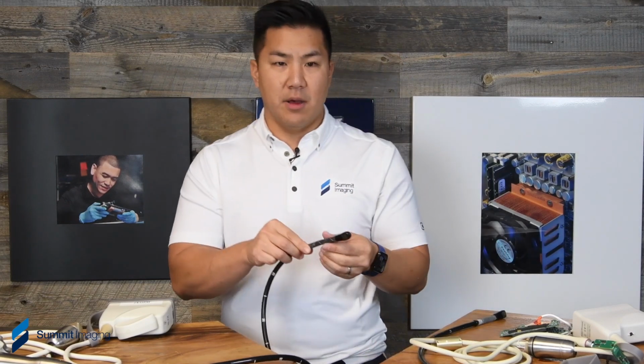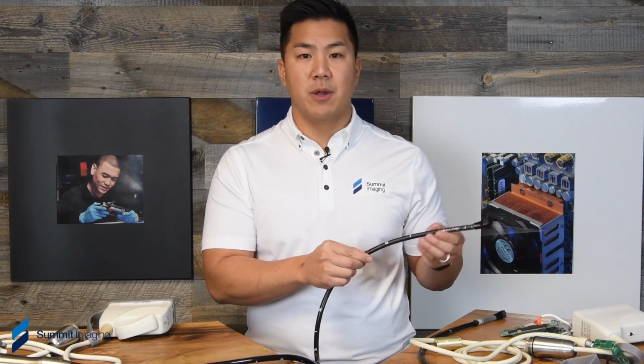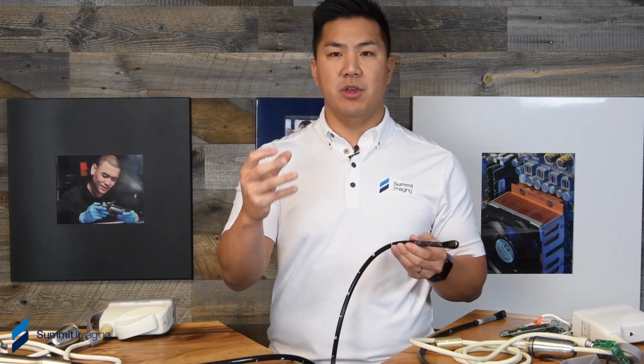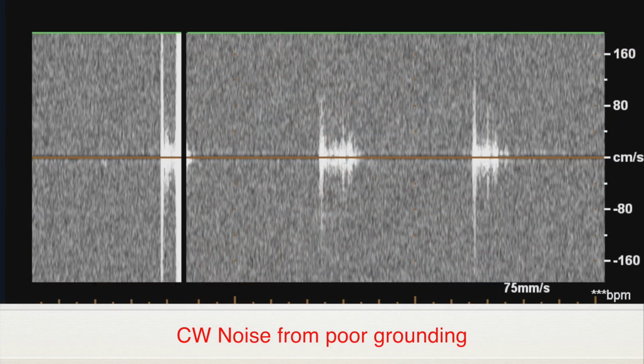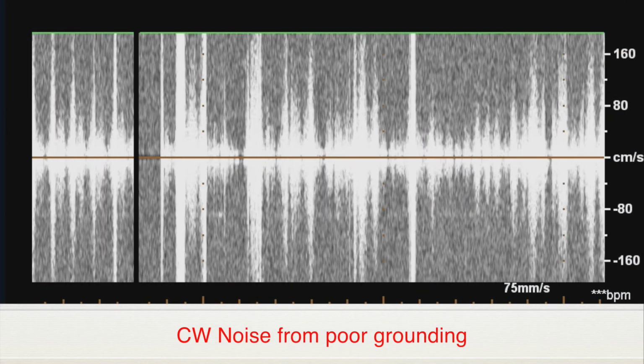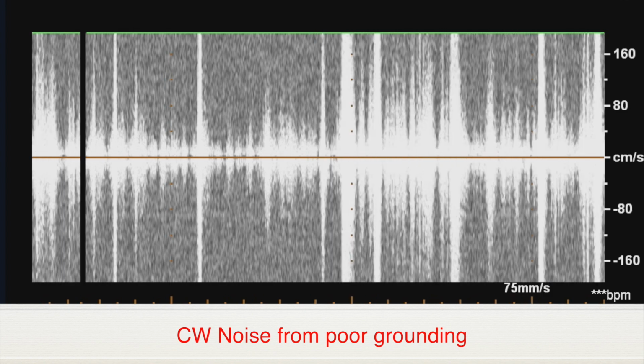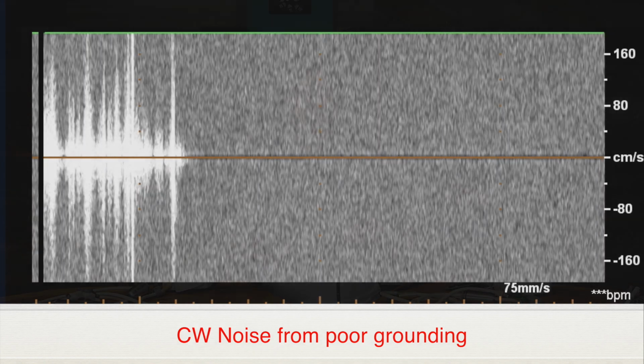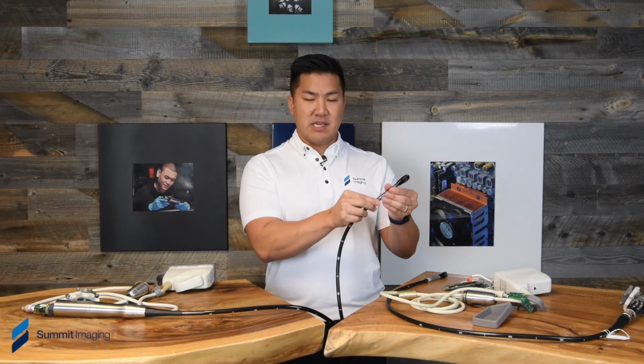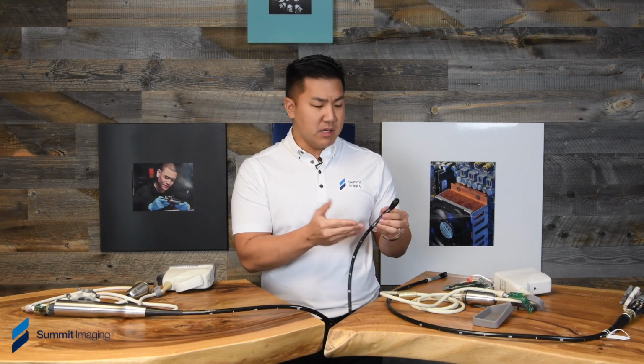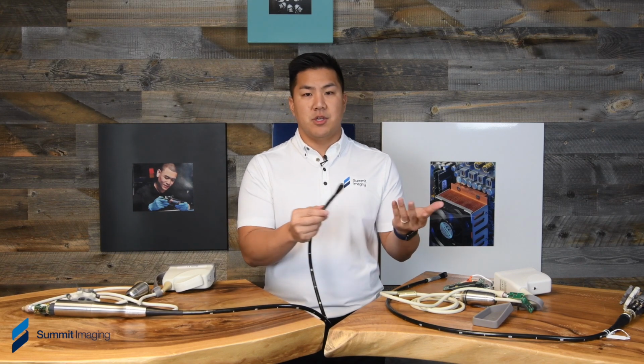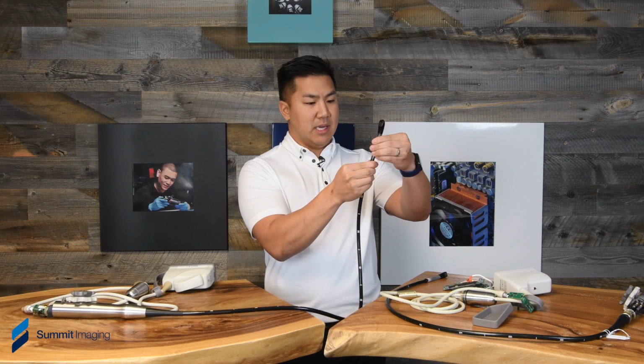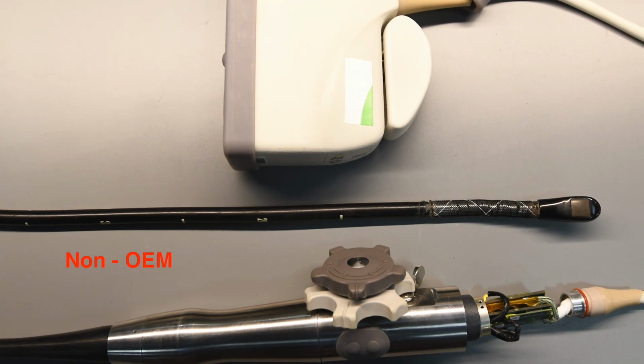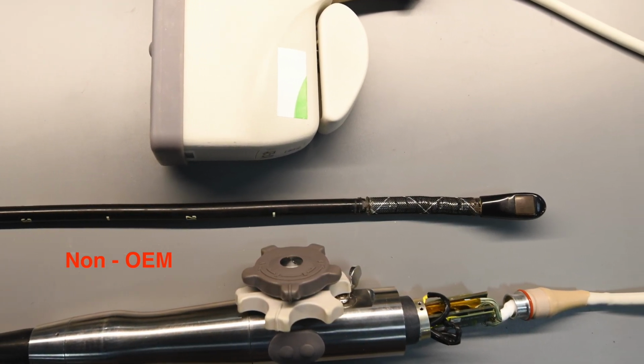So as this is being moved around inside the patient to get a great image, you're going to be seeing this background CW noise coming in and out by virtue of this not properly being grounded and introducing noise of metal sliding on metal, and these are extraordinarily sensitive. It's going to catch that. So we don't want a misdiagnosis because this isn't properly attached, and in our opinion this is a very basic repair that should have been done in the first place. But as you can see, this is moving around, it's going to cause noise and therefore compromise the efficiency or accuracy of the study that this probe is being used for.